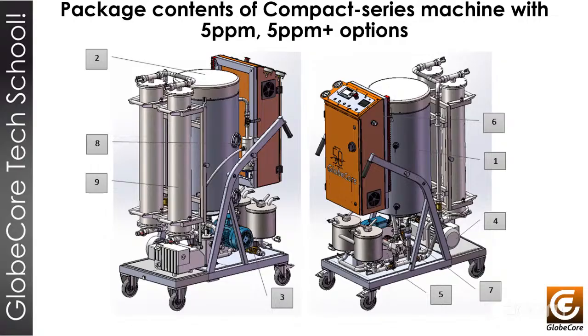It's really easy to change these filters. You see here it is not a really complicated system to replace every cartridge of Zeolite, and that will help the performance of the filtration of the oil.